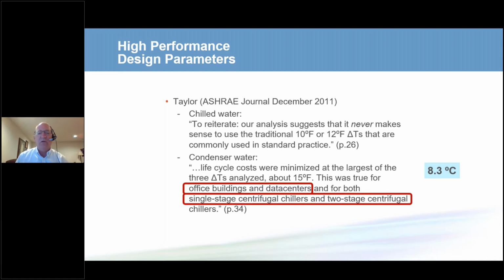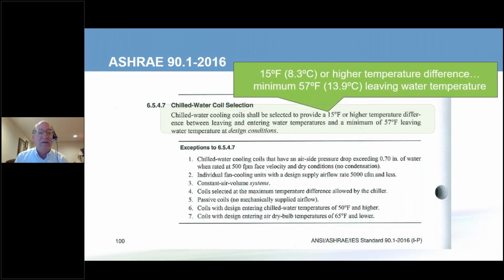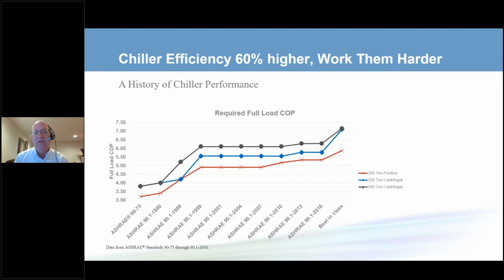The second thing he said, there are often claims made that this is only for one chiller manufacturer or a few chiller manufacturers. And Mr. Taylor got information from all the chiller manufacturers and found that no matter the chiller design, whether it's a screw chiller, a scroll chiller, a centrifugal chiller compressor, whether or not it has a variable speed drive, reducing the flow rates and increasing the delta T makes sense. As I stated, ASHRAE Standard 90.1 2016 and 2019 require that 8.3 degrees C delta T and require our coils to be selected for that. Now, there are some exceptions, for example little fan coils, but everything in the industry is telling us to go toward higher delta Ts and lower flow rates.